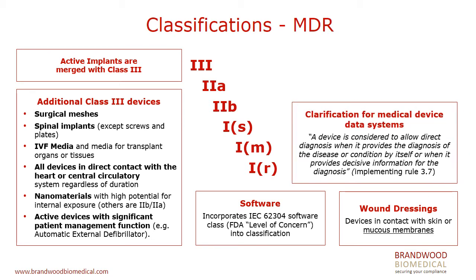There are clarifications, again coming back to software, for medical device data systems. This has been an area of confusion for a long period of time. Devices which connect to other diagnostic medical devices, things making diagnostic measurements, may have devices that then move that information around. For example, devices for telemedicine may connect with something like an ECG and shift the information from the ECG to a remote location for display on a screen where it may be reviewed by a clinician, or an X-ray image or something like that.